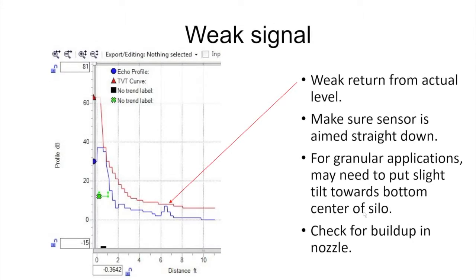In this example we have a very weak return from our actual level. In fact looking at the graph here, the echo does not even exceed the red TVT line so it will not be considered as a potential actual level.